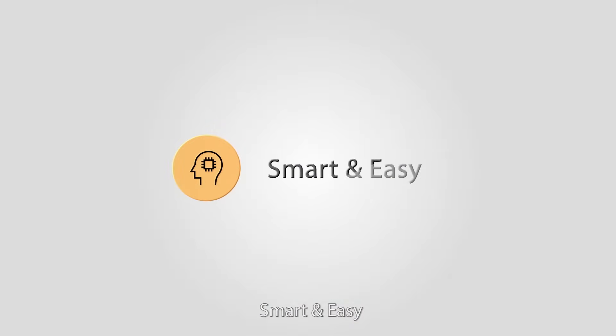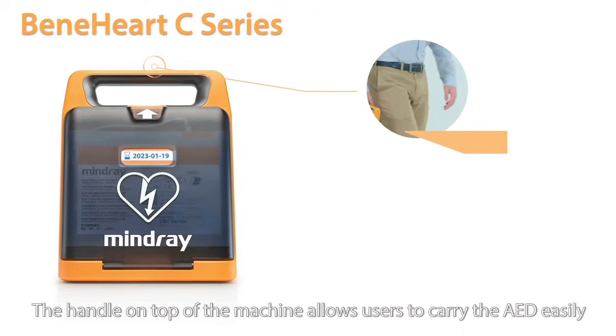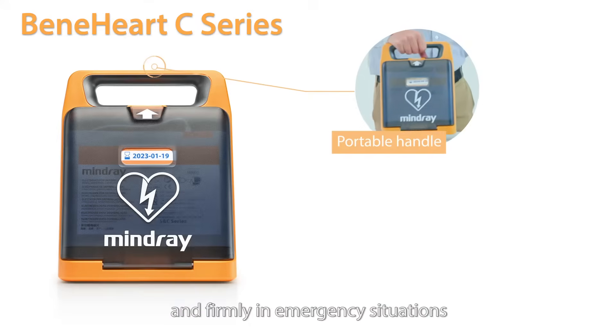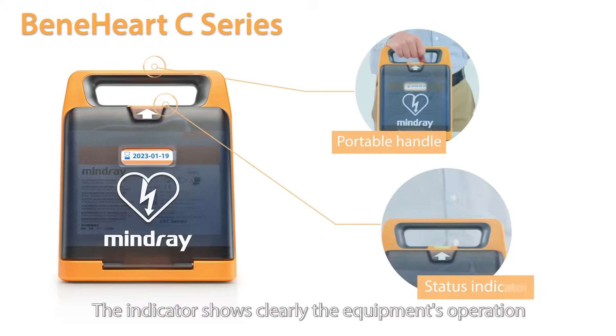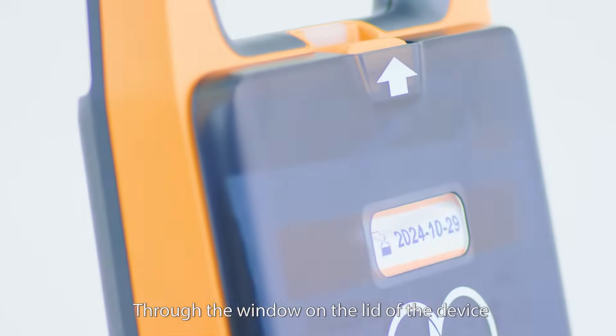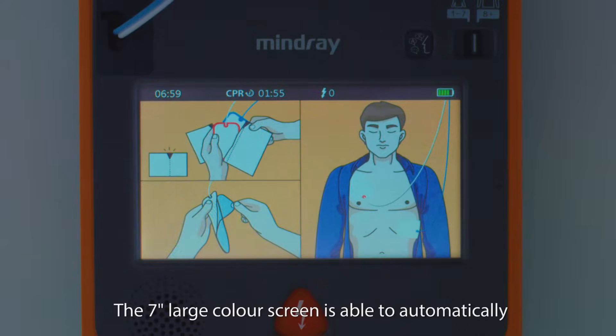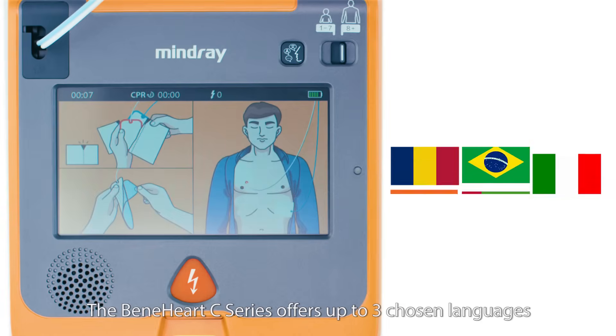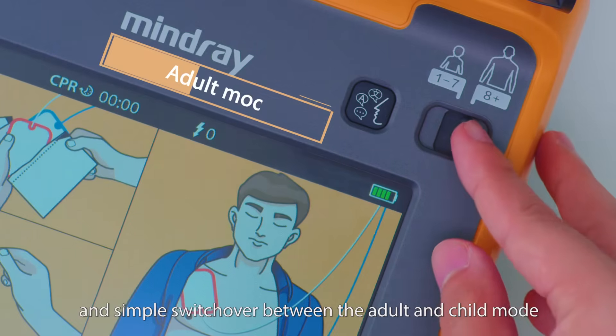Smart and easy. The BeneHeart C Series AED is smart and easy to use. The handle on top of the machine allows users to carry the AED easily and firmly in emergency situations. The indicator shows clearly the equipment's operation status with different colors. Through the window on the lid of the device, users can check the pad's expiration date. The 7-inch large color screen is able to automatically adjust screen brightness to different environments.